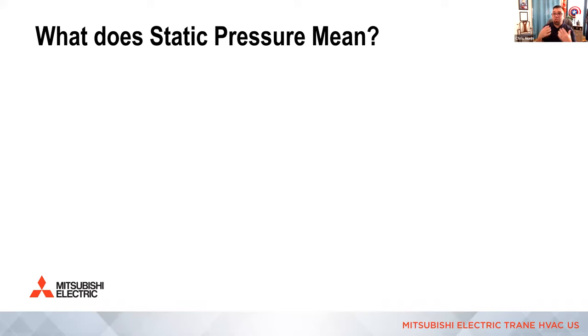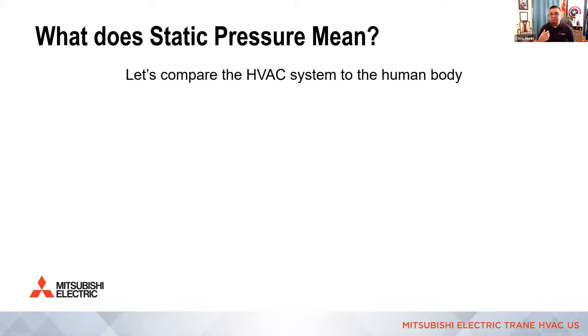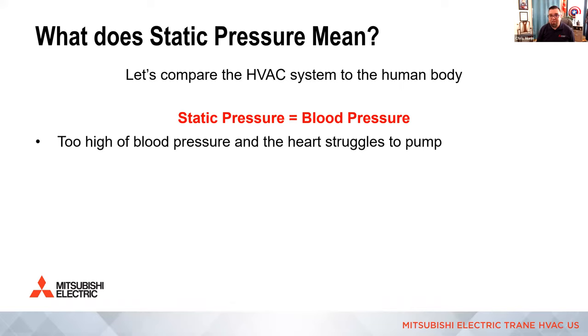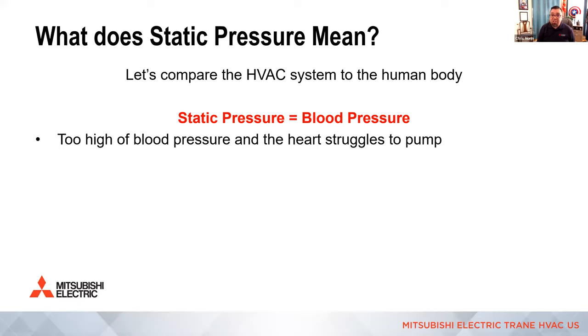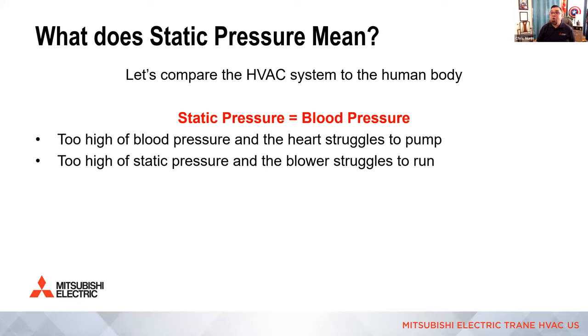So static pressure, what I want you guys to understand is it's kind of like blood pressure, all right? So the higher the blood pressure, the worse our bodies are, right? We can only overcome so much. We have an amount that's supposed to be. If it's too low or too high, we have a problem. And static pressure for any ducted system is the same thing, right? Too high blood pressure, heart struggles to pump. Too high static pressure, the blower struggles to run, or we drastically increase the kWh of that ECM motor in order to deliver that same volume of air, all right?